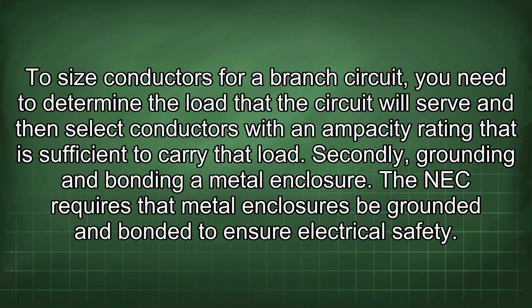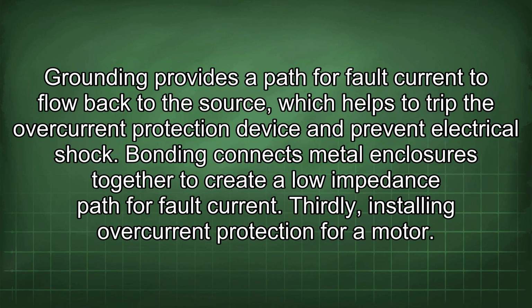Second, grounding and bonding a metal enclosure. The NEC requires that metal enclosures be grounded and bonded to ensure electrical safety. Grounding provides a path for fault current to flow back to the source, which helps trip the overcurrent protection device and prevent electrical shock. Bonding connects metal enclosures together to create a low impedance path for fault current.